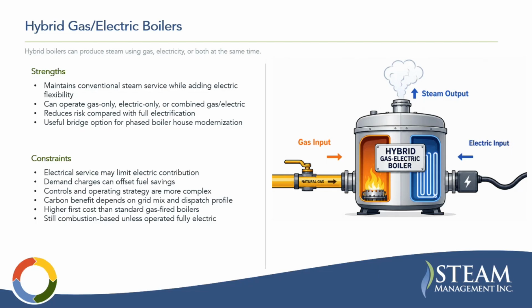Some constraints: electrical service may limit the electric contribution. Demand charges can offset fuel savings. Controls and operating strategy are more complex. The carbon benefit depends on the grid mix and dispatch profile. There's a higher first cost than just a standard gas-fired boiler, and they're still combustion-based unless you're operating fully electric. I will note some boiler manufacturers now are leaving a space for a future immersion heating element for electrical support or electric steam production. So basically leaving the possibility to integrate that into the boiler down the line.